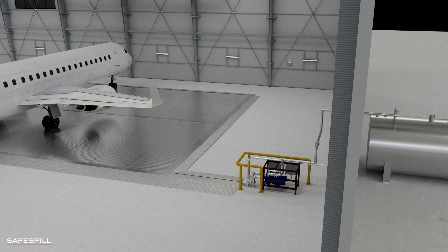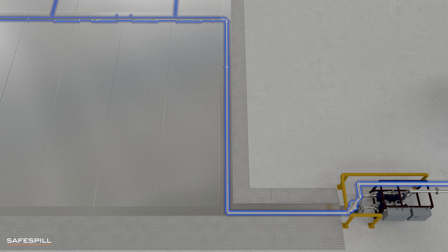Now let's look at the flushing system. The typical slope of a hangar slab is 1%, or 0.5 degrees, resulting in a relatively slow drain rate. To accelerate spill removal, a water-based flushing system is integrated into the Safespill Floor.